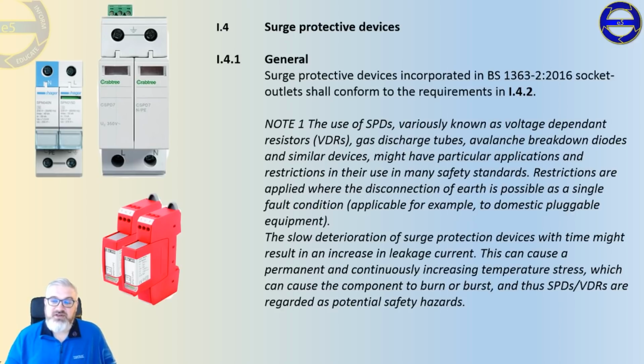So the slow deterioration of surge protection might increase leakage current. This causes a permanent and continuous increase in temperature stress, which can cause the component to burn or burst. Thus, surge protection devices are regarded as safety hazards. Now, it's fairly evident I have two standards that potentially are conflicting, and yet we as electricians are being told, go and fit surge protection devices, do the formulas, do the risk assessment, but when we do it, we end up being told you have to do it anyway.